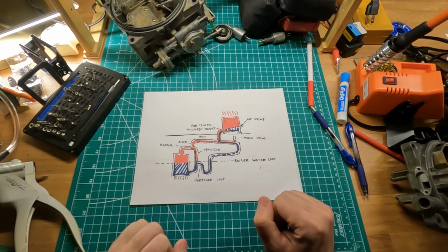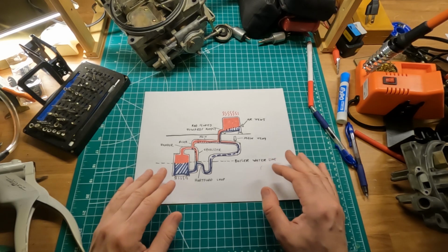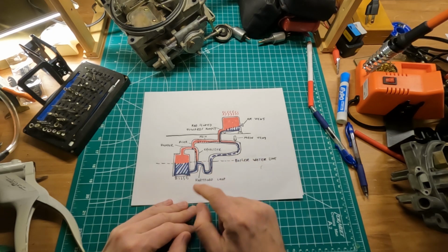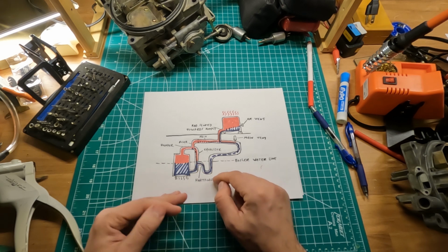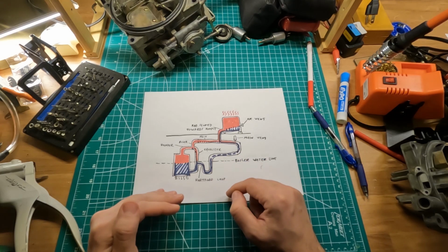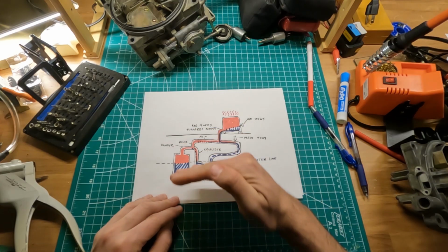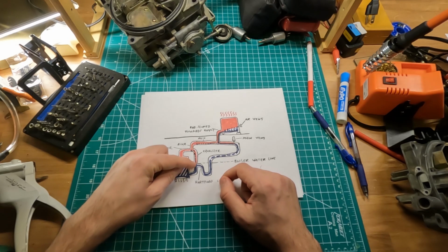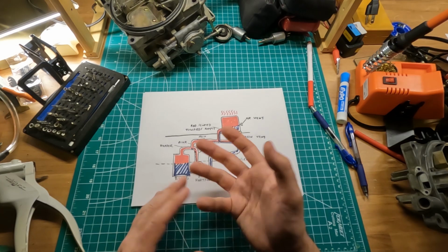And that's a realistic view of how the steam heat system looks in a residential building. As you can see, you have the boiler water somewhere here. If you notice, the Hartford Loop is below the boiler water, so it has to be high enough to prevent lots of water loss in case there was a leak somewhere happening here. At the same time, it has to be low enough so that when the water level moves up and down because of the boiling function, there is no steam entering the Hartford Loop, and that prevents a water hammer.